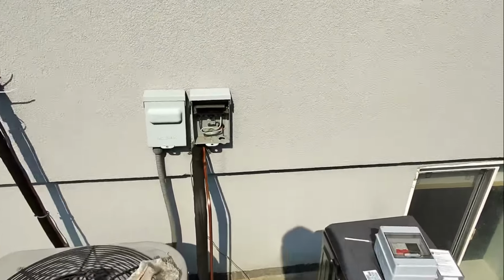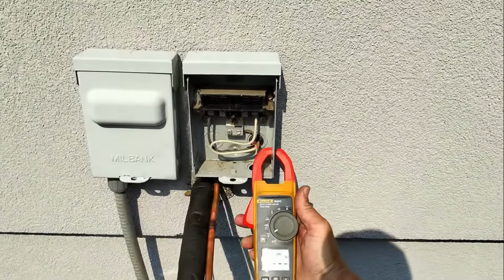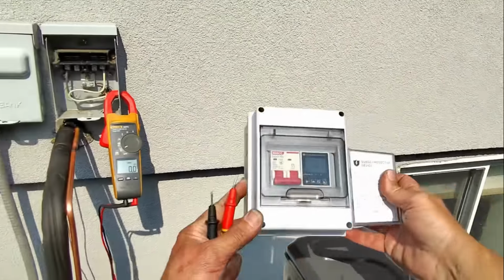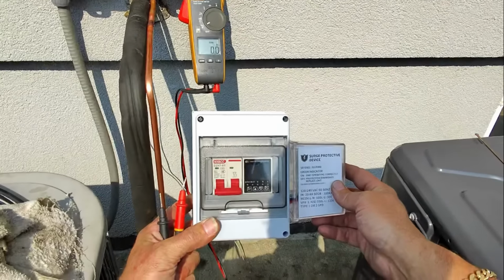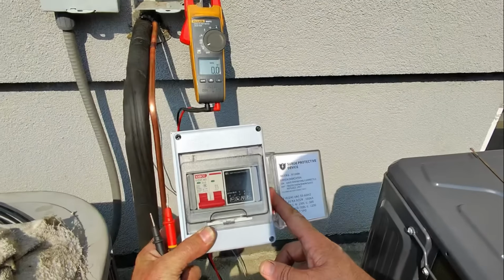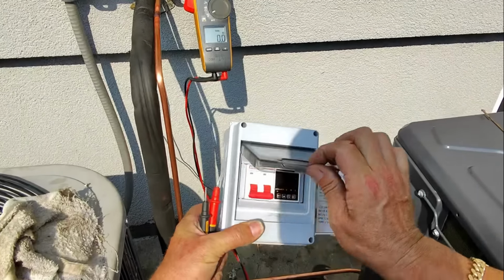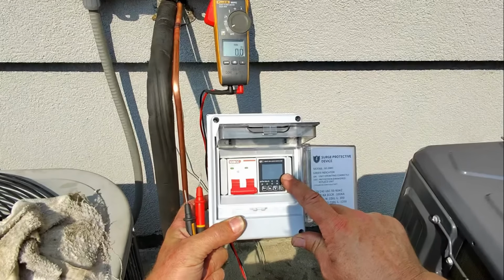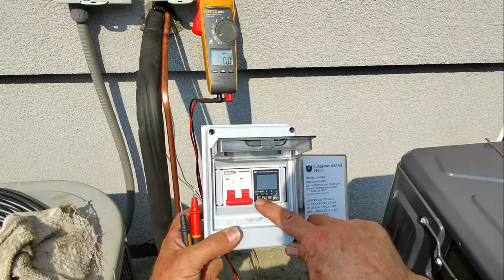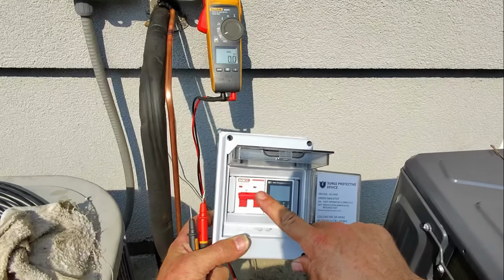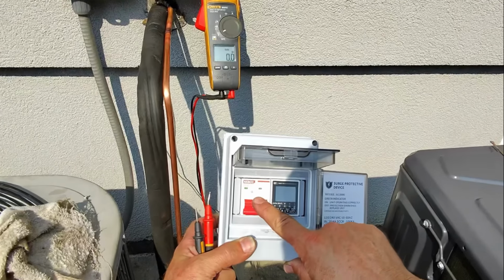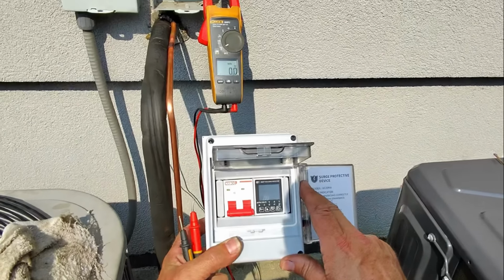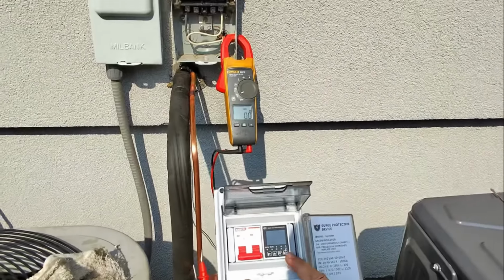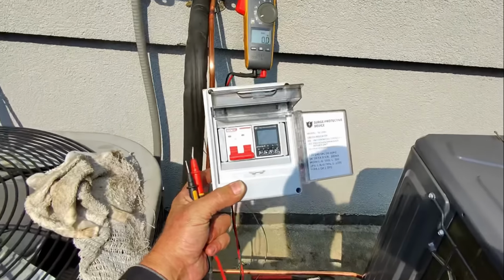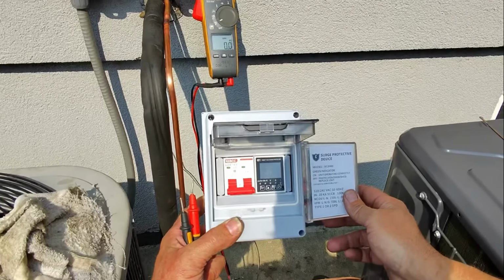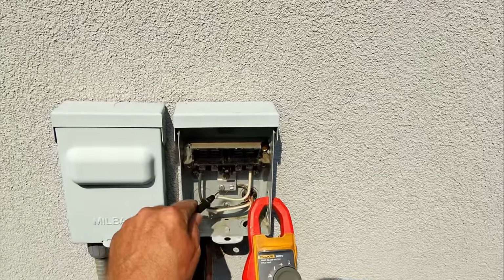All right folks, we're going to work on this disconnect box. I love to do one better than the last, but on every install I replace the disconnect and install my custom invention, the Mikey Pipes power management system. This is a surge protection device attached to the plastic weatherproof box. Under the hood we have a digital smart reclosing protector which senses under and over voltage and shuts the system down. You can connect it to Wi-Fi and download the app. And then we have a 63 amp miniature circuit breaker here. This is all mounted on a rail inside this box, designed to replace a disconnect box right there. We're going to put this on, connect it, and create a whip from the box to the equipment, basically providing a premium insurance policy for this equipment, ensuring the inverter is protected for years to come. All right, let's check for voltage again.